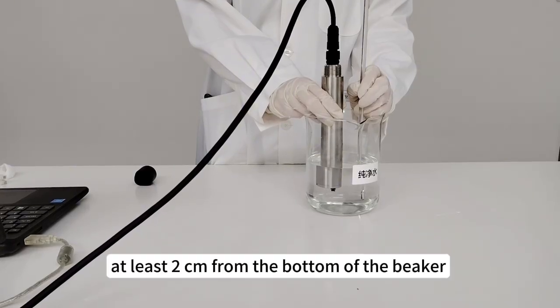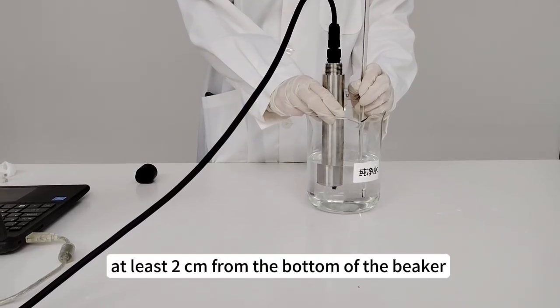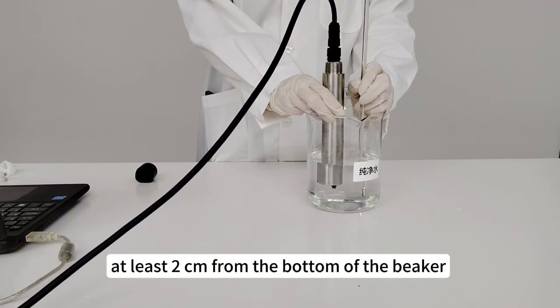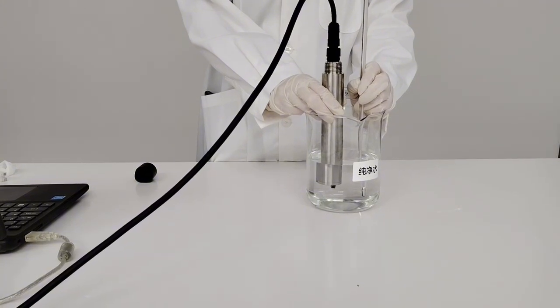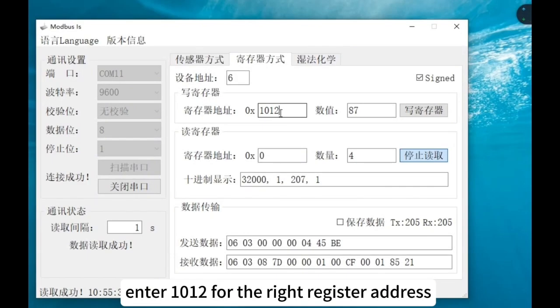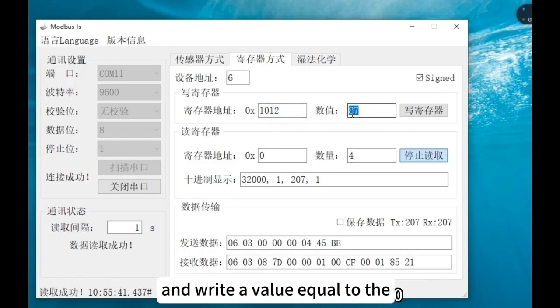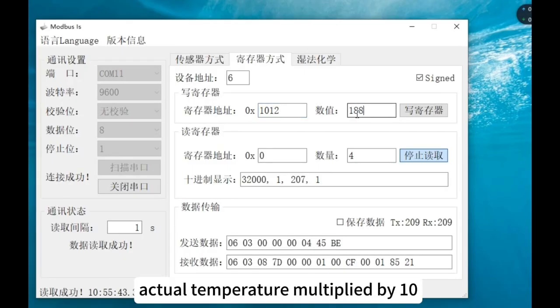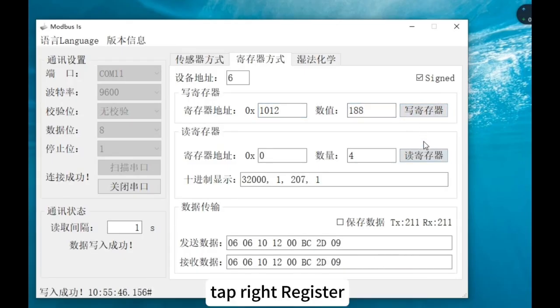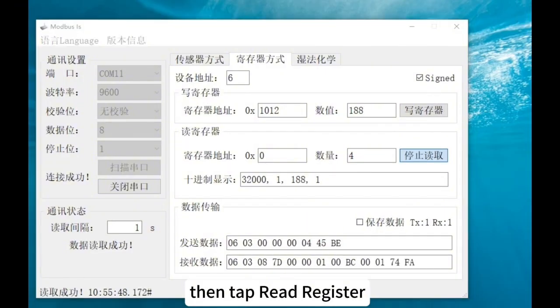Place the sensor at least 2 centimeters from the bottom of the beaker. Enter 1012 for the write register address and write a value equal to the actual temperature multiplied by 10. Tap Write Register, then tap Read Register.